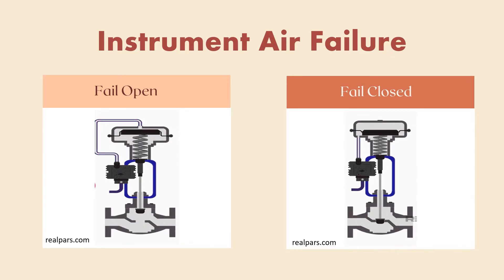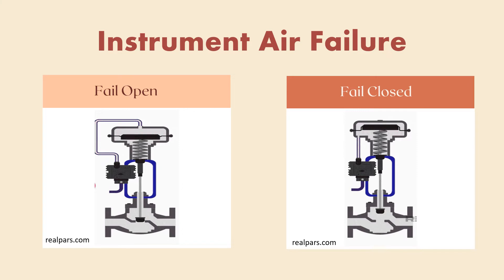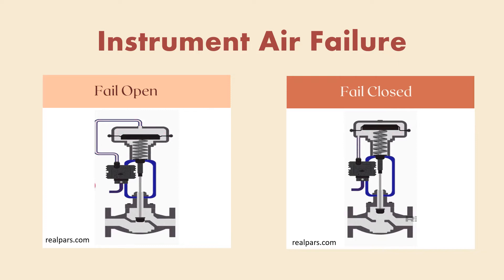This should be determined case by case. In the same plant, we may have valves with a fail open action, others with a fail closed action, and sometimes failing in the last position. But at the end, we should ensure that the valve fail action shall be the fail safe position, which is the position that will be safer for the plant.